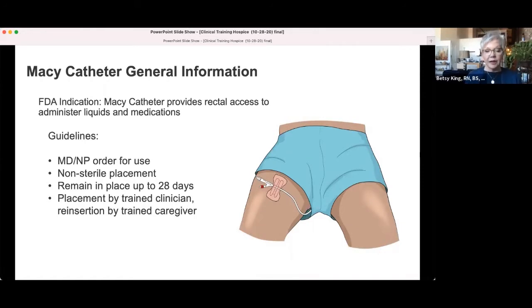And once inserted, again, it just remains in place by the small retention balloon, and it can stay in place for up to 28 days. The reason for that is because the balloon is very soft, very pliable. It doesn't put any pressure on the mucosa of the rectum, so there's no necrosis or no issues there. It also doesn't innervate the pudendal nerve, so the patient doesn't have a feeling that they need to bear down or defecate. It's really very comfortable for the patient, and they're just not aware of it after you've placed it.